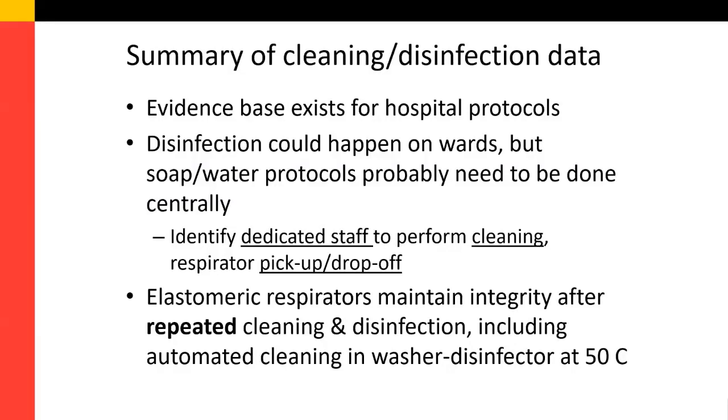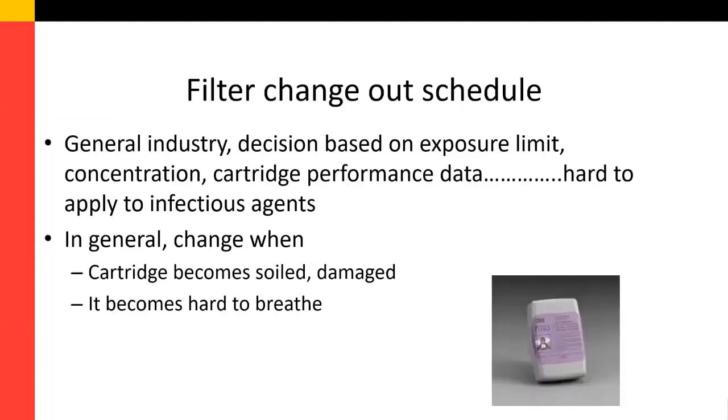The key thing here is that there needs to be dedicated staff to perform the cleaning, as well as assigned people to pick up and drop off the respirators. And importantly, elastomeric respirators maintain their integrity after repeated cleaning and disinfection, including automated cleaning in a washer disinfector at 50 centigrade.